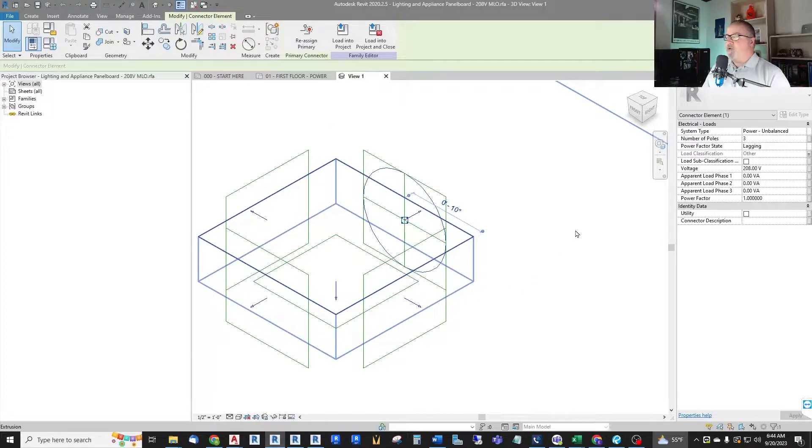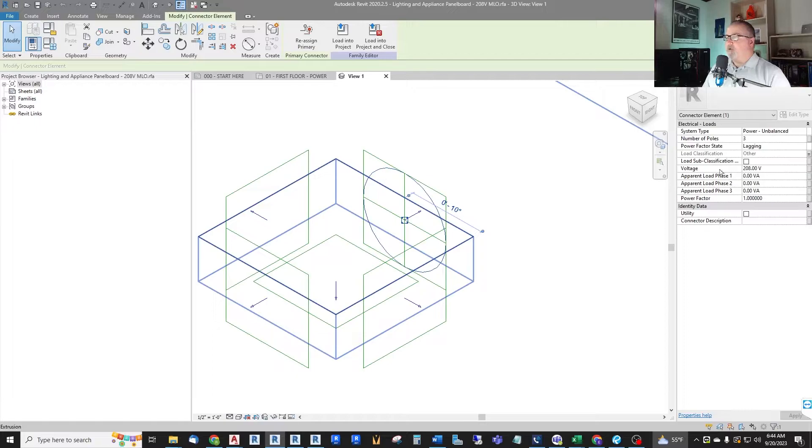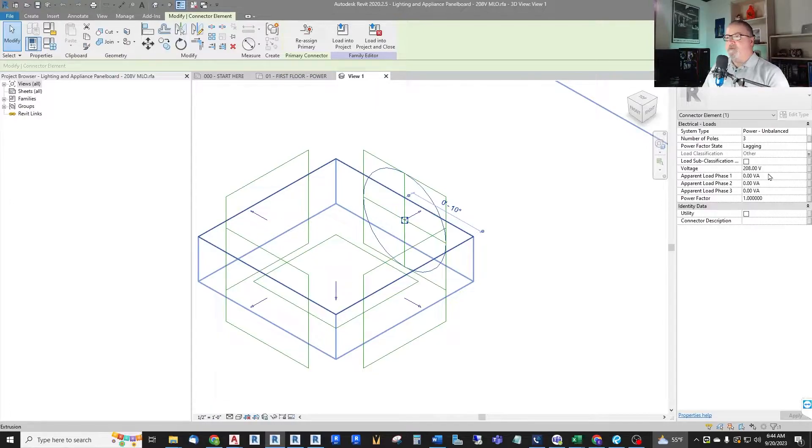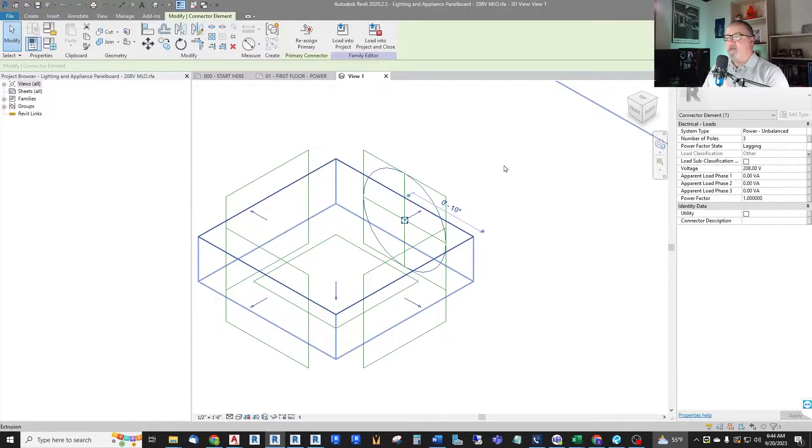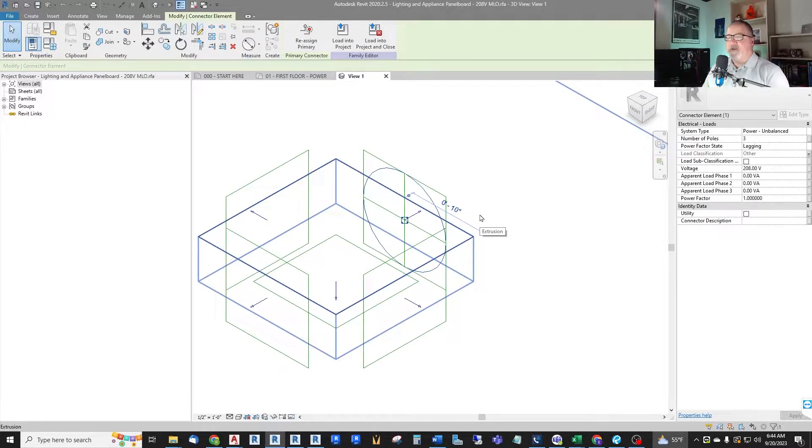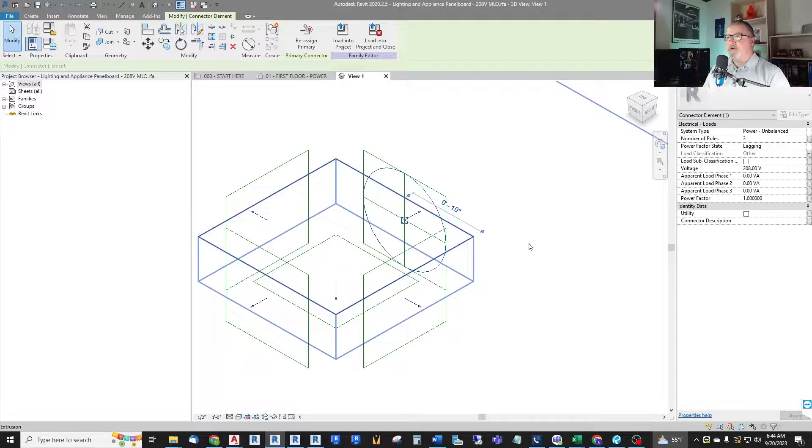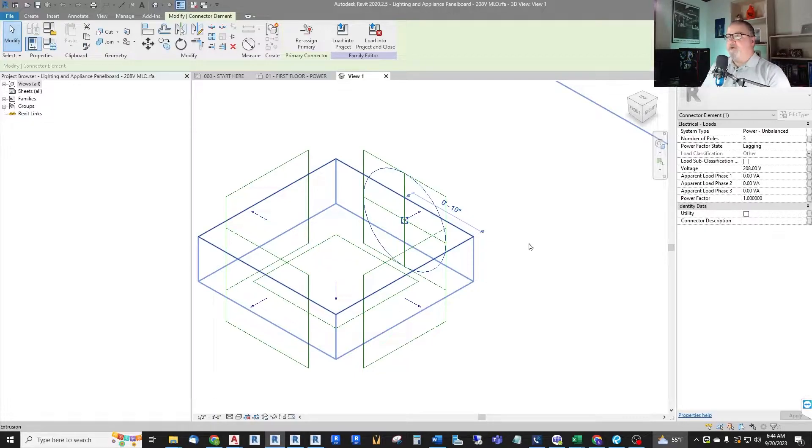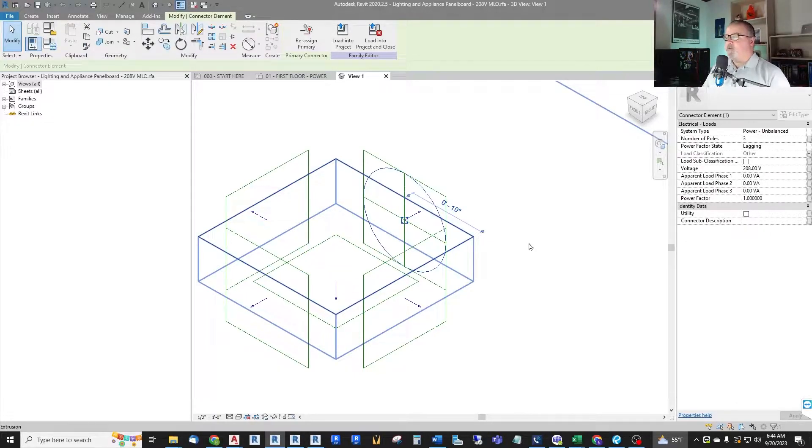Now we could map these internal parameters from this connection to the family if we want so we can change it in the model, or we could hard code this one as a 120/208 two pole single phase panel and just have it that way. So it's up to you how you want to do this for your end users. I've kept them hard coded for the other panels so I'm going to keep this one hard coded this way.